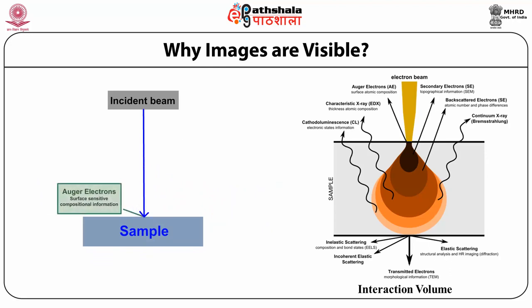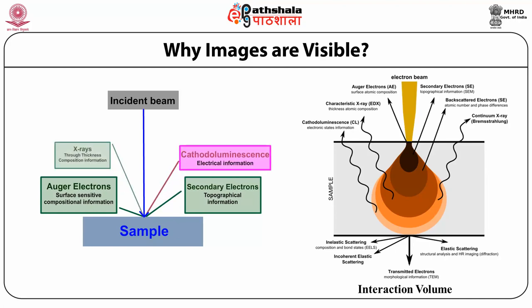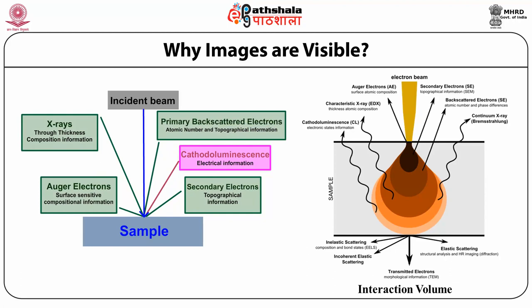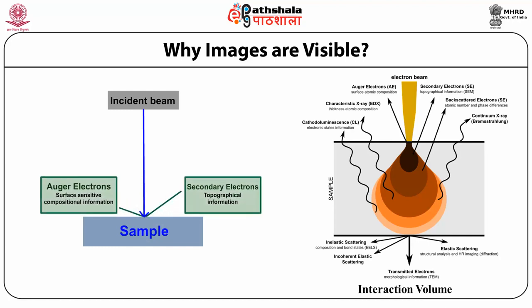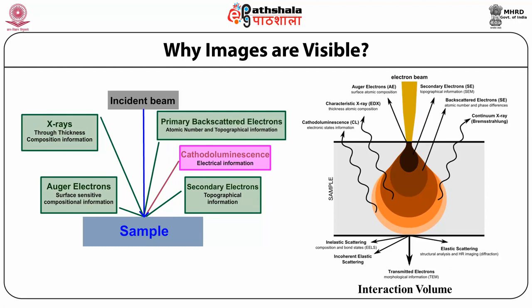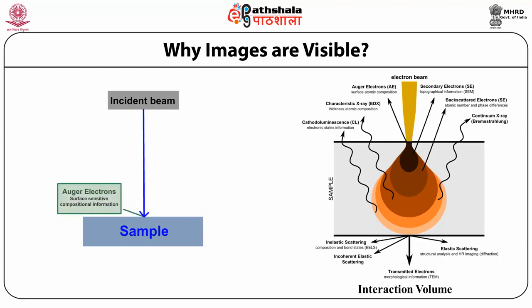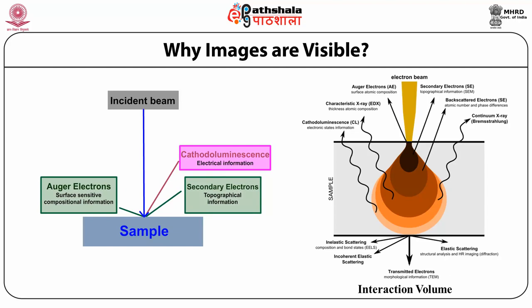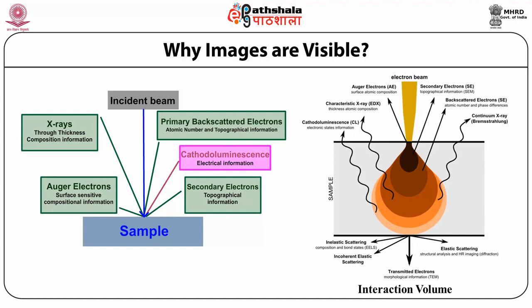When the primary electron beam interacts with the sample, the electrons lose energy by repeated random scattering and absorption within a teardrop-shaped volume of the specimen known as the interaction volume, which extends from less than 100 nanometers to approximately 5 micrometers into the surface. The size of the interaction volume depends on the electron landing energy, atomic number of the specimen, and specimen density. The energy exchange results in reflection of high-energy electrons by elastic scattering, emission of secondary electrons by inelastic scattering, and emission of electromagnetic radiation, each detected by specialized detectors.